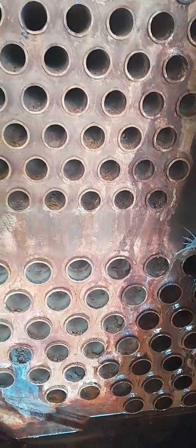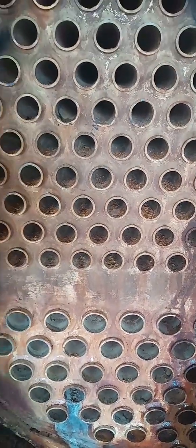Also, we look at the TDS. TDS is the total dissolved solids. This majorly comes from the residue of the chemicals that we dose into the water over time. This can also affect the efficiency of your boiler. They settle at the bottom of your boiler, so this needs to be checked and monitored often. If you measure and the value of your TDS is high, you should increase your blowdown frequency so that the efficiency of your boiler could be okay.